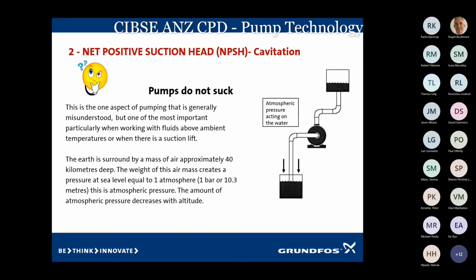We get the pump to work by atmospheric pressure. So the pump, even though it's full of water and it's primed, it just won't pull the water. Atmospheric pressure, which is holding all of us down, is actually pressurizing onto the water. The value of that atmospheric pressure must be great enough to overcome the losses in the foot valve, the pipe work, the static height, and anything else between the water and the pump intake. And then the pump will work quite happily.